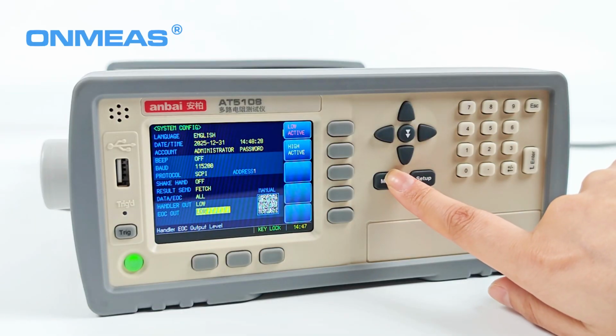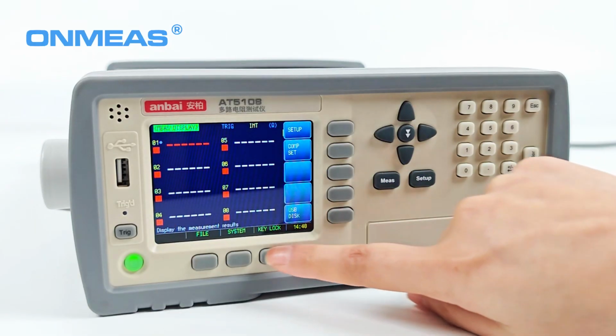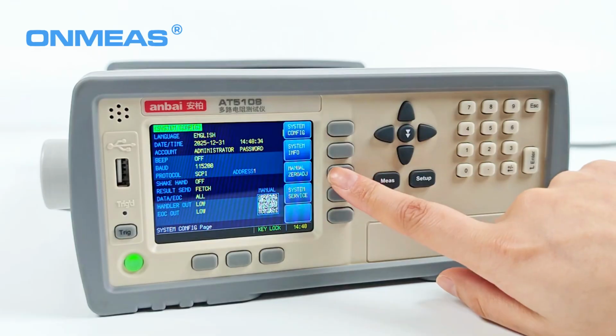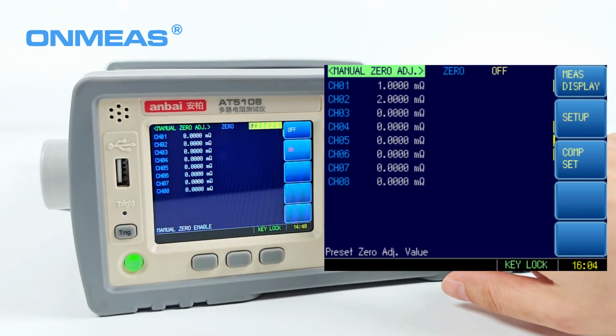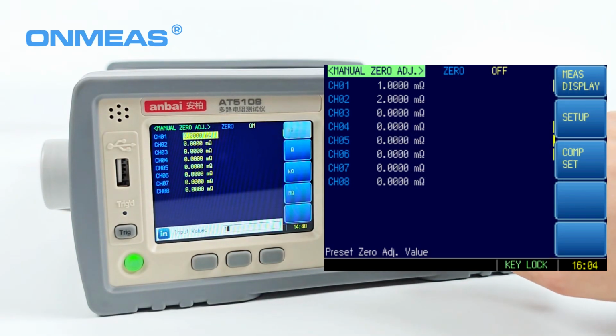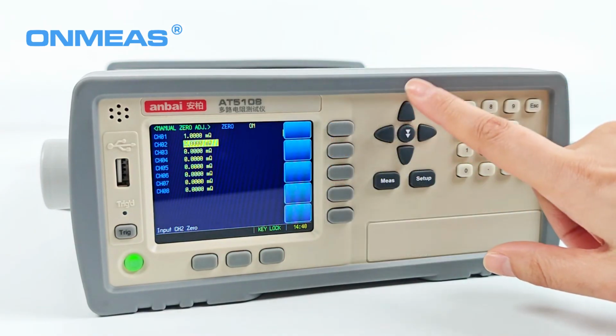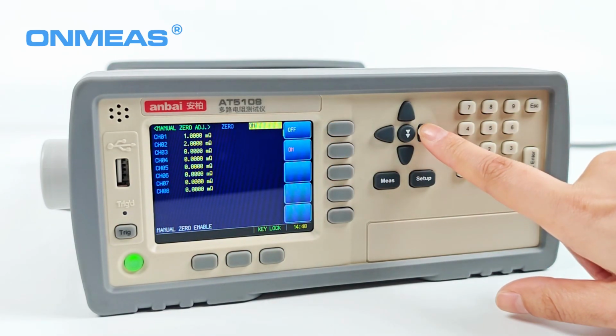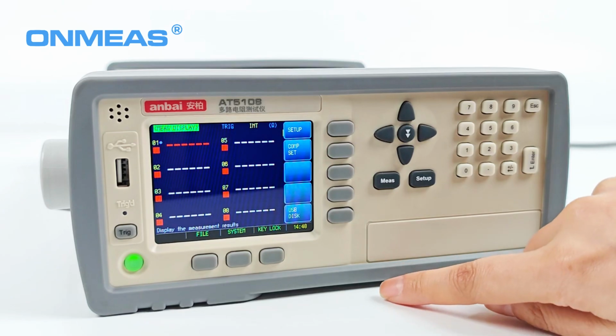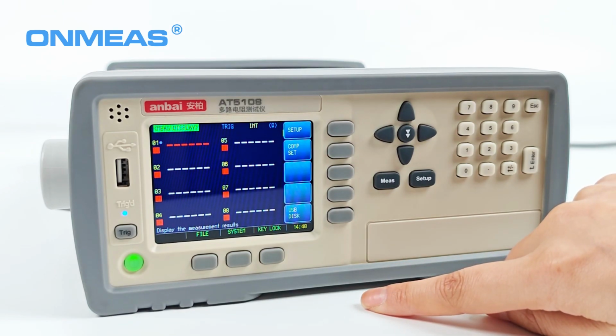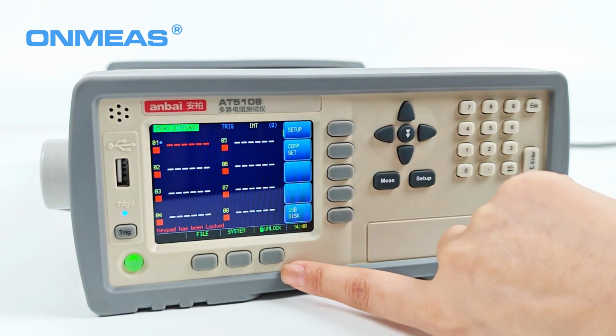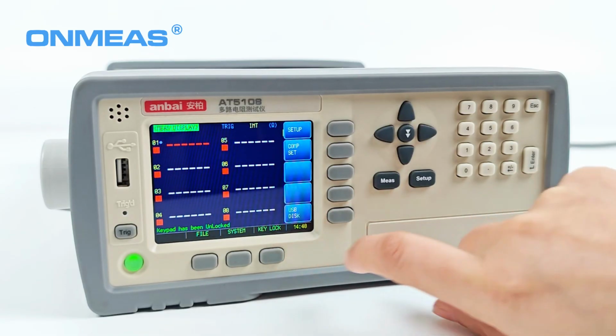Press Zero Value Correction to enter the Zero Correction Reset page. On this page, you can set whether to enable or disable the zero value. Users can set the reset value for any channel as needed. After selection, they can input the value using the numeric keypad. The function keys offer one-click locking and unlocking. Once locked, no other keys can be used.